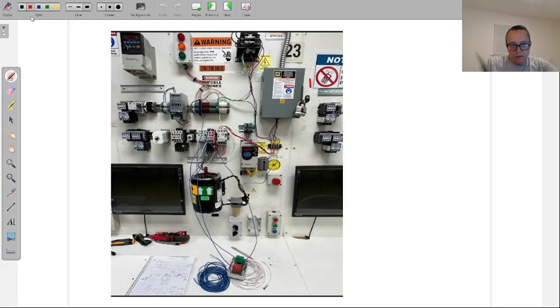Where's L1 and L2? We just got a piece of paper that says L1 and L2. So this is what I was saying yesterday: motor control lives on paper, and it lives in the physical sense. So looking at a piece of paper that says L1 and L2, now where do I find this? Phil is walking you through a lot of this, but L1 and L2 will be located at a specific point, so I can measure my voltage between L1 and L2 there and confirm I have power, because if I don't have power, it's just like troubleshooting a regular circuit.